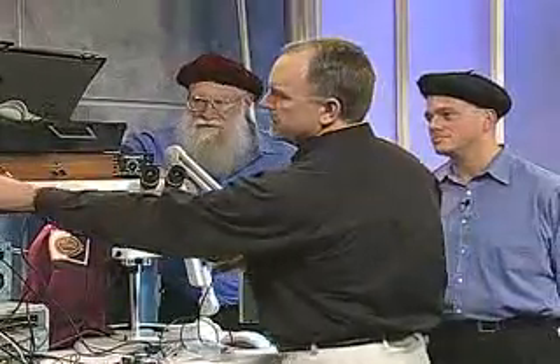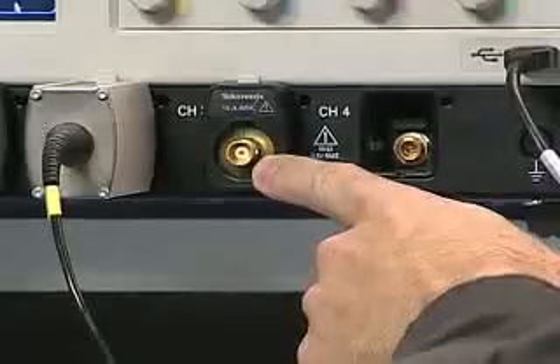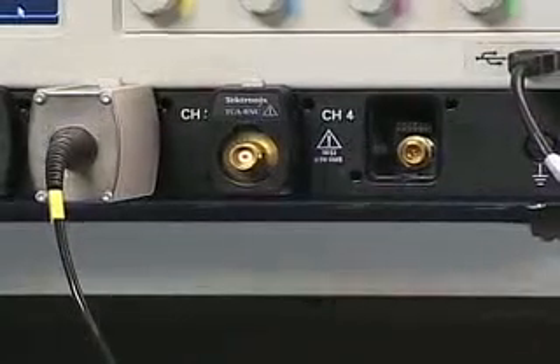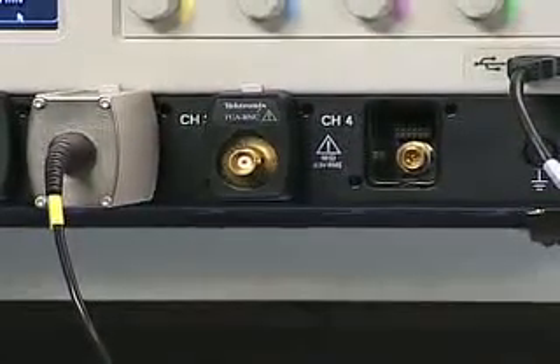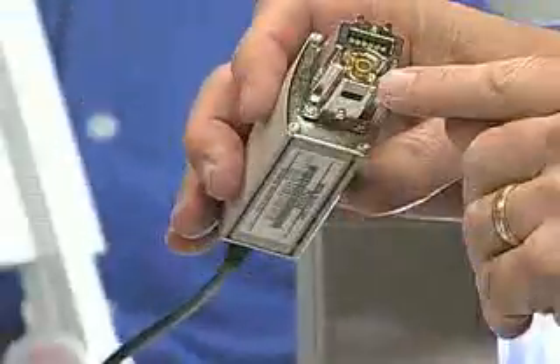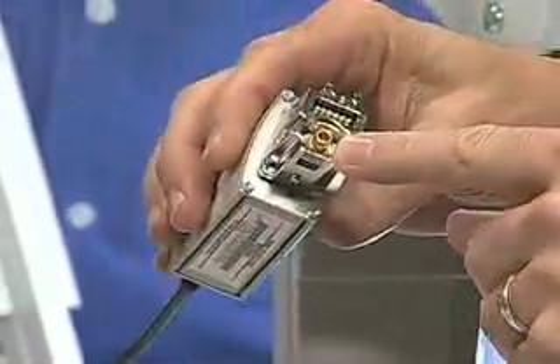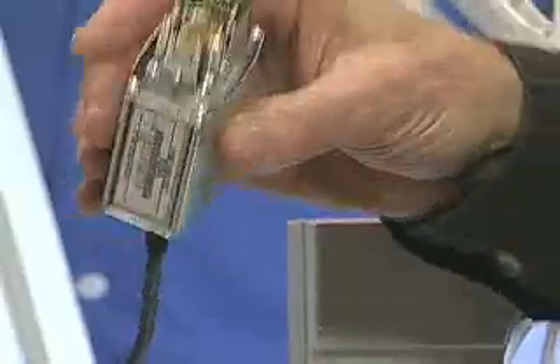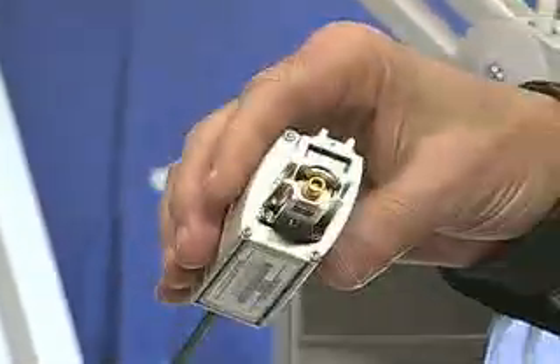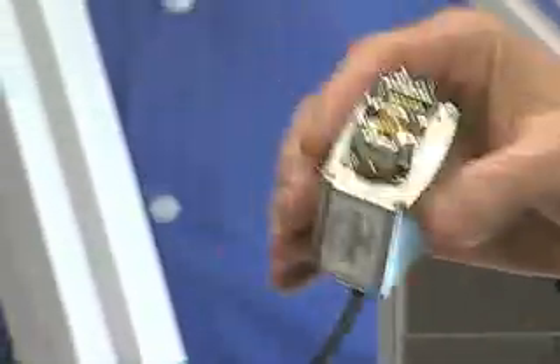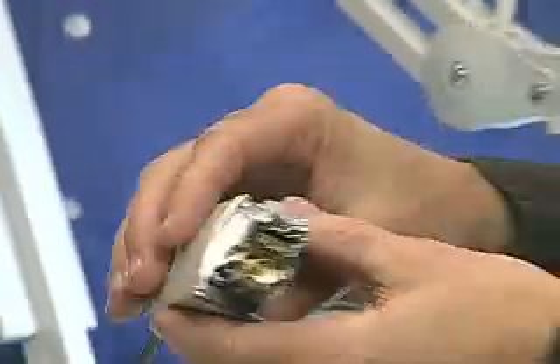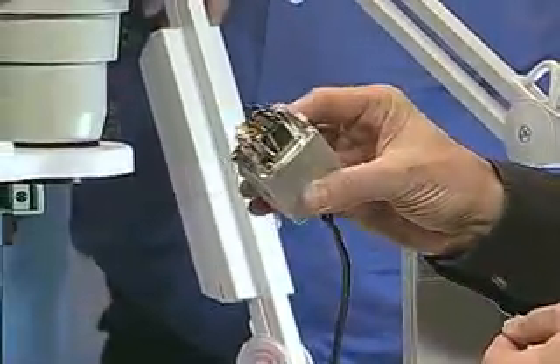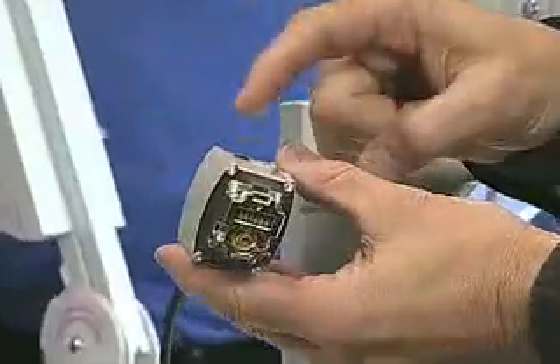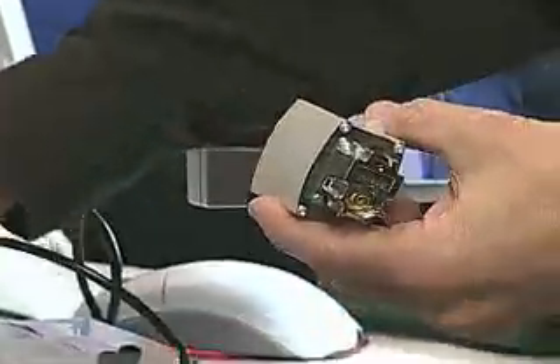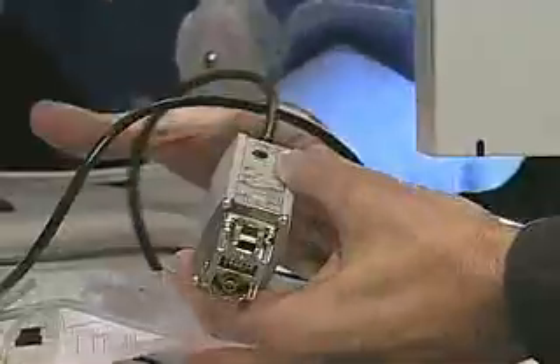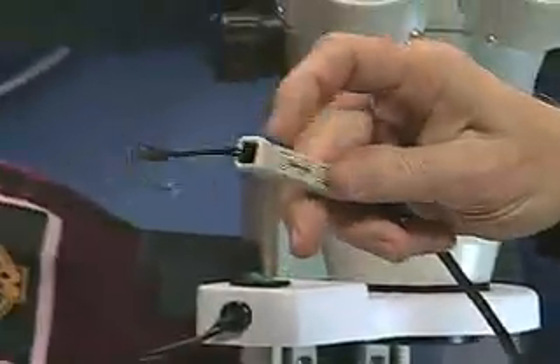The BNC that you may be more used to really runs out of steam at about between 3 and 4 gigahertz. About 3 and 4, yeah. So as we get higher and higher bandwidths, we had to go to a more reliable 50 ohm connection and also a more intelligent connection so that the probe can communicate with the scope. So it can tell the scope what its properties are, what its parameters are, even what kind of voltages it needs, because we've got, in this case, a silicon germanium differential amplifier down here in the probe head.